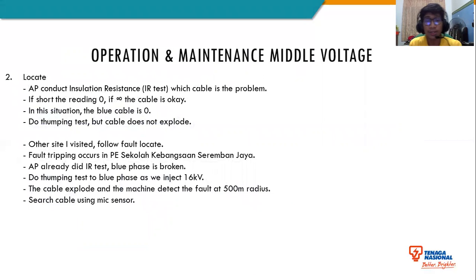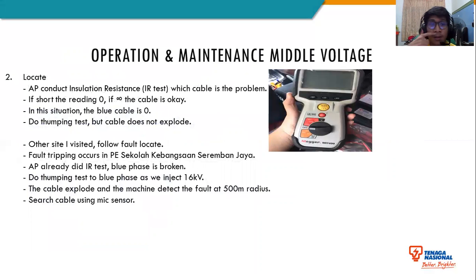Then we locate. The AP will conduct an insulation resistance IR test to find which cable is the problem. If short, the reading is 0. If infinity, the cable is okay. In this situation, the blue cable is 0. So we do a thumping test, but the cable does not explode. This is because the cable is already broken.